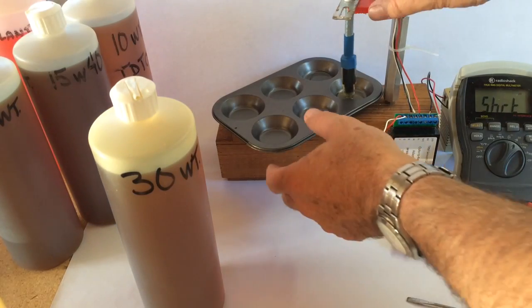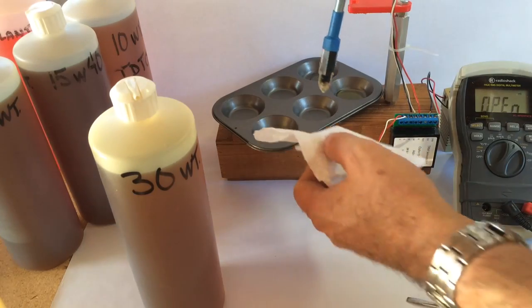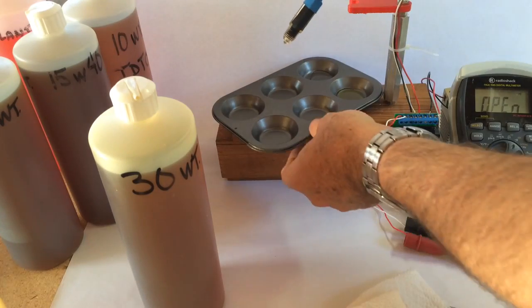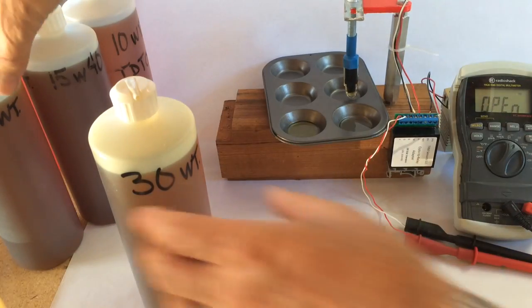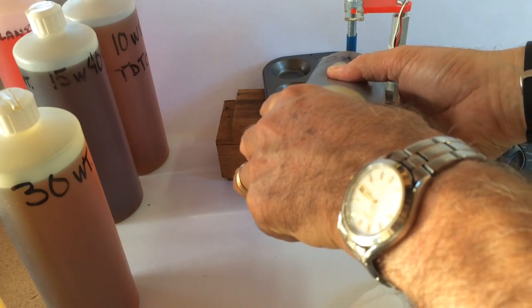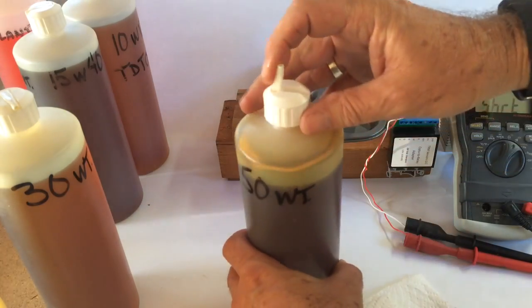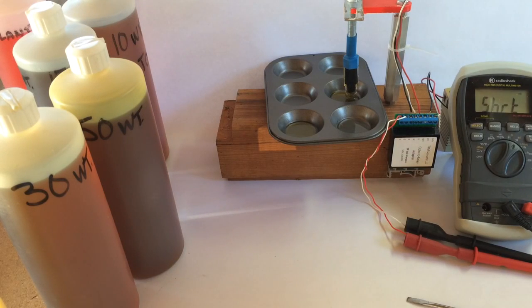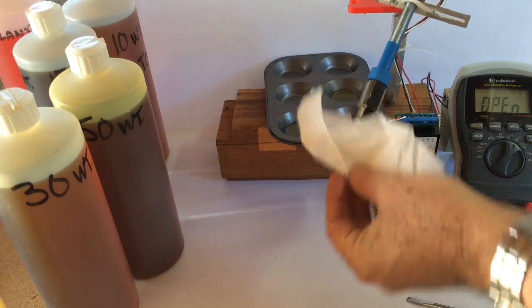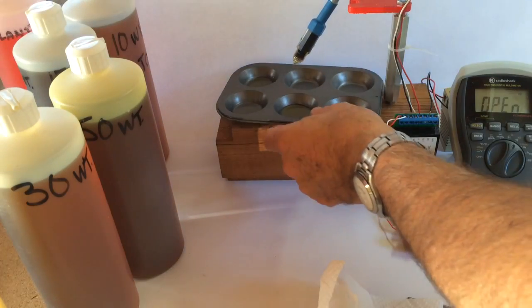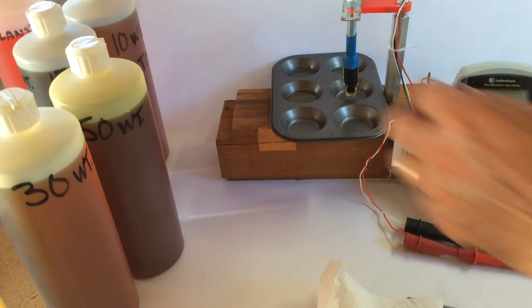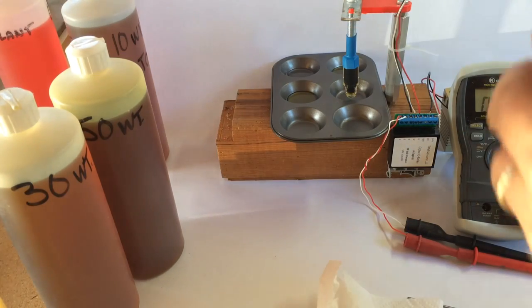So again, it triggered with just barely enough oil to cover the bottom of the tin, in fact not even completely. We'll move on to the next one. This is 50 weight lube oil. It looks like the response time in all these oils is probably less than 2 or 3 seconds, starting from when the oil actually contacts the probe. This last of the lube oils is 15W40.